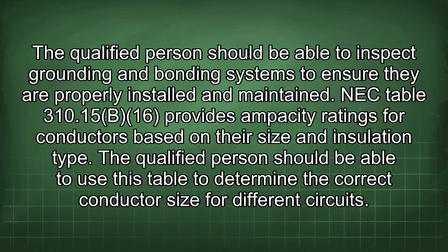The qualified person should be able to inspect grounding and bonding systems to ensure they are properly installed and maintained. NEC Table 310.15(B)(16) provides ampacity ratings for conductors based on their size and insulation type, and the qualified person should be able to use this table to determine the correct conductor size for different circuits.